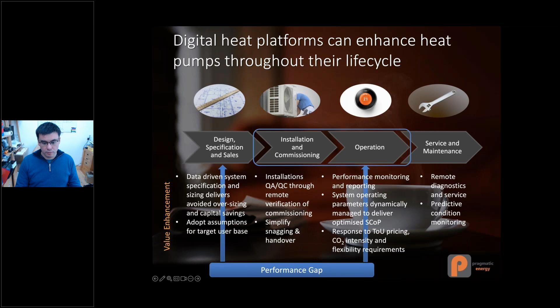The biggest issue is that it's not standardized. Everybody's doing it in a slightly different way, and quite often they make you pay for it, or they only allow access to trained installers, etc. But the key message out of this slide is there's lots of tools required. Perhaps the bit in the middle is the problem, and that's where we really see a performance gap happening: the difference between what you've designed up front, what your SAP score or EPC rating is based on, and the actual operation of the heat pump.